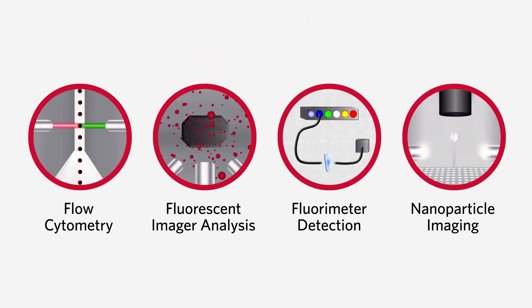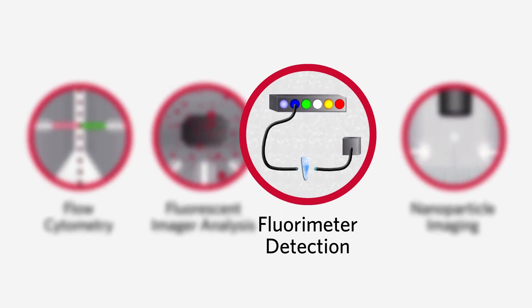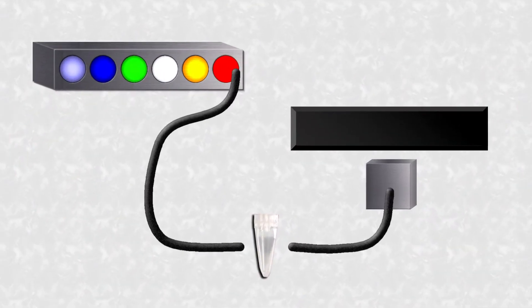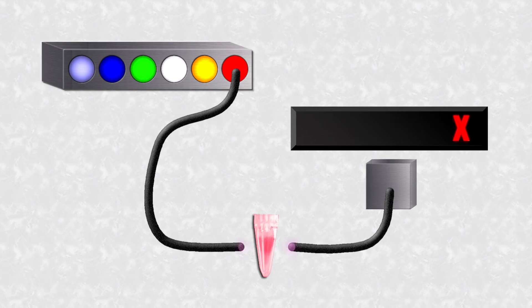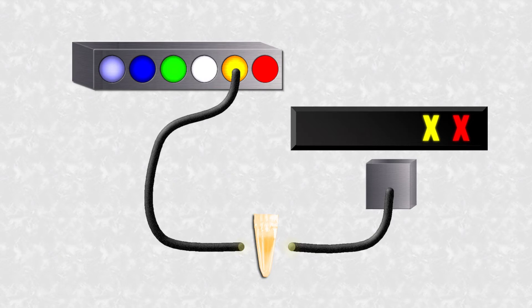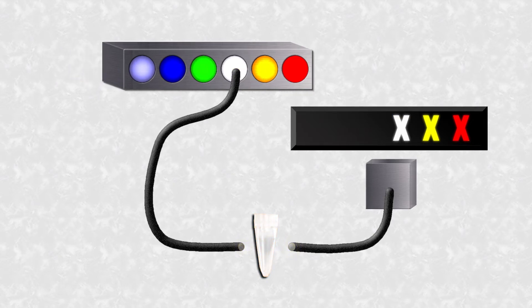Another detection method Luminex uses is fluorimeter detection. This method uses 6 LEDs that shine on 6 photodiode detectors using fiber optic cables. Each LED is a different wavelength and will excite different reporters.